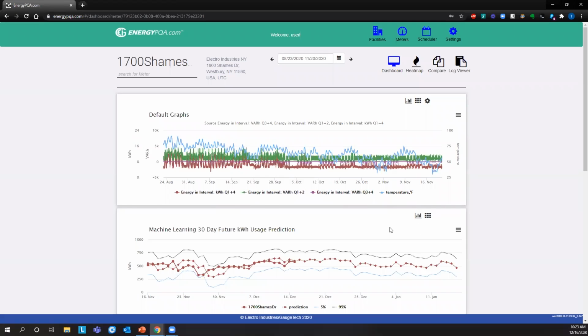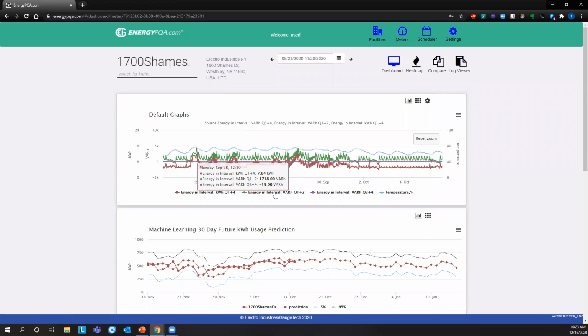So if these are getting too condensed together, we can always click and drag on an area to zoom in. And if I hover over kilowatt hours, quadrants 1 and 4, it will gray out everything else and bring this energy in the interval value to the front, so I can see exactly what I'm using. You'll also notice over here that we have multiple scales. Our kilowatt hours and kilovar hours are fairly similar, but if you wanted to look at voltage and current, your voltage at 120 volts and your current at 10 amps, instead of having current at the very bottom looking like 0, Energy PQA will create a new trend for that.